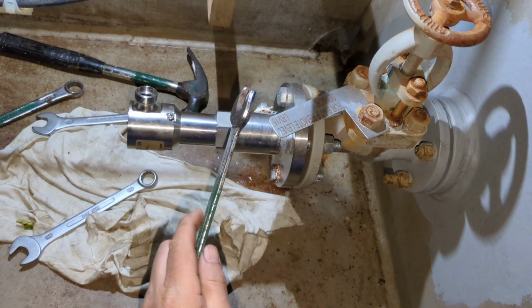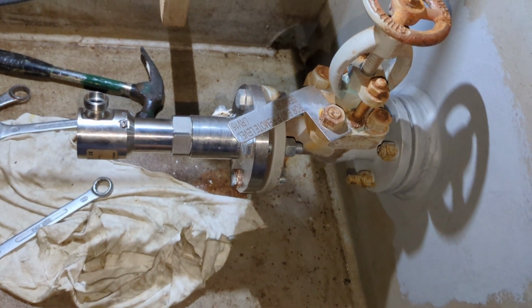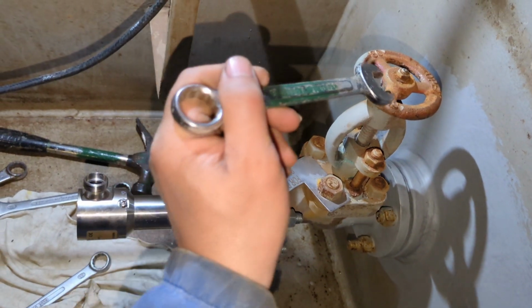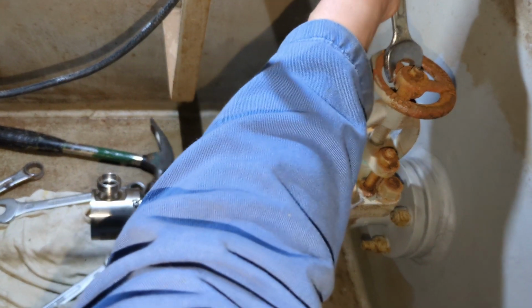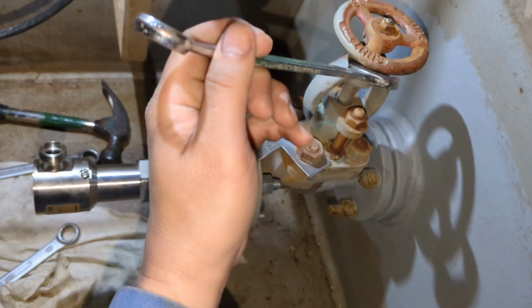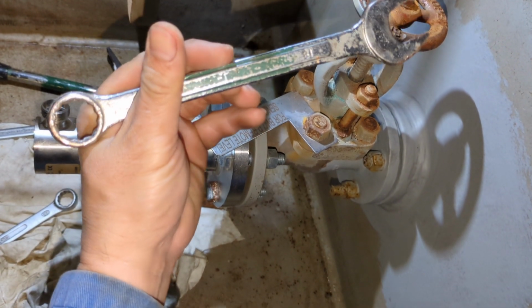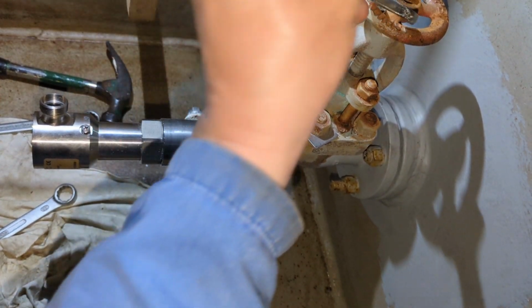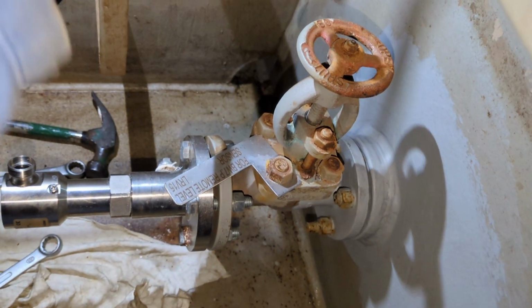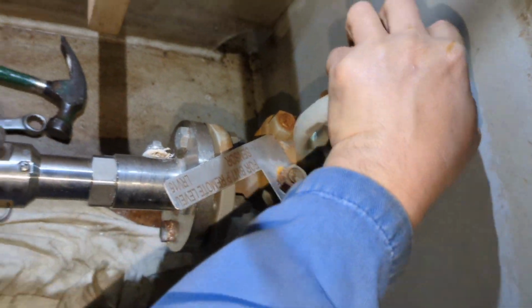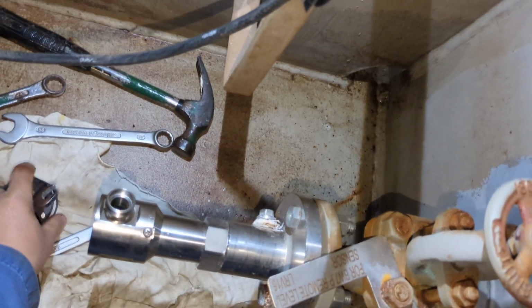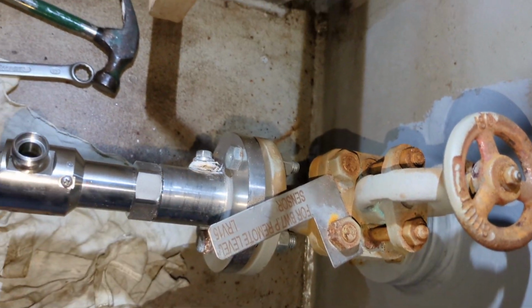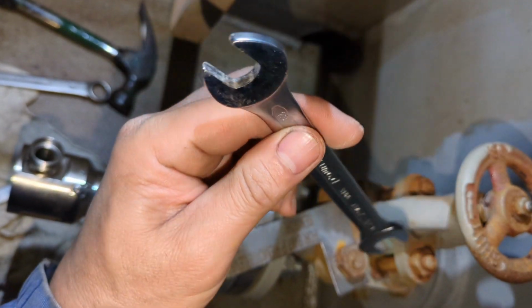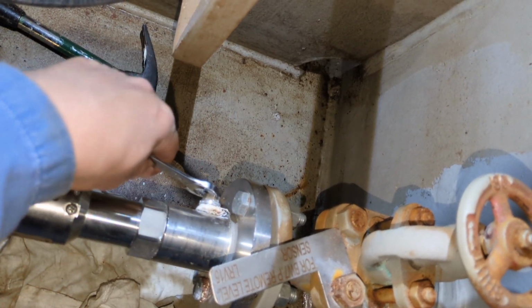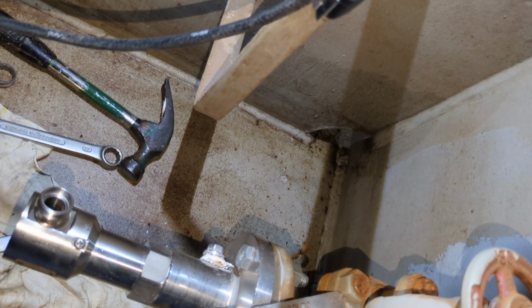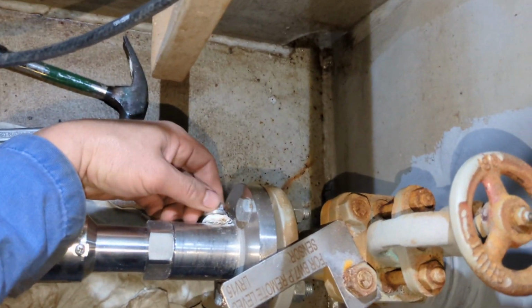Guys, before replacing any sensor like this, you must make sure that this valve is fully closed. So just now I closed it using number 19 spanner. No, that is 18. So we can close it. Now it is closed, so we can open the bleeder. There is a bleeder here, but to open it, just use number 13 open wrench.